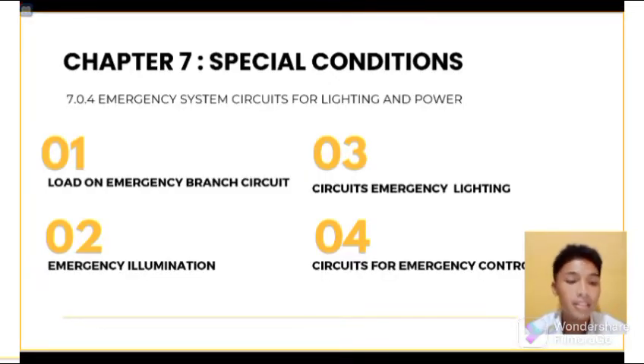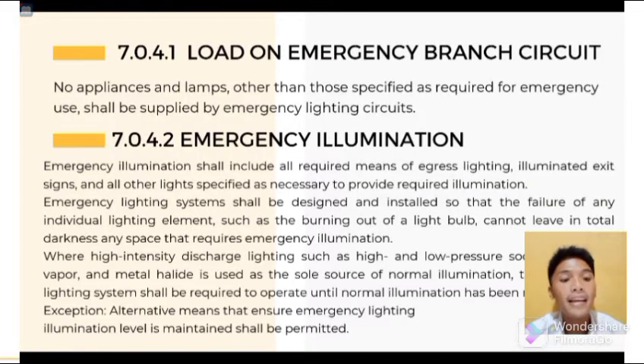7.0.4 Emergency System Circuit for Lighting and Power. 7.0.4.1 Loads on emergency branch circuits. So, no appliances and no lamps other than those specified as required for emergency use shall be supplied by emergency lighting circuits. So, wala po daw na appliances or no lamps that will be connected or supplied by emergency lighting circuits.